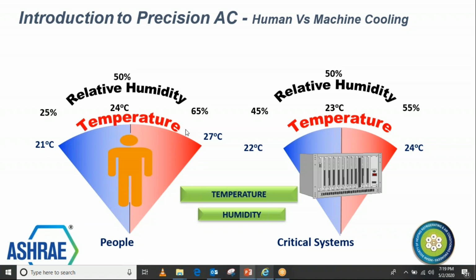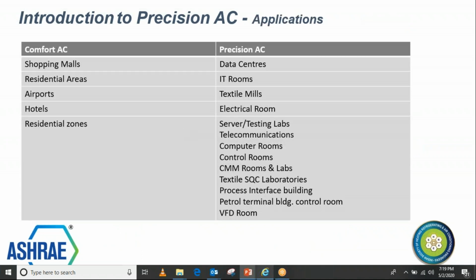And here this gives you a little idea of the application differences. This will also give you an idea that comfort air conditioning is designed to fit shopping malls, residential areas, airports, hotels, and obviously other residential zones. The reason for this is that when you design the evaporator coil or the fans, the sensible heat ratio, the airflow, and the overall design of the unit to fit that application, it is different, and it's designed for comfort.